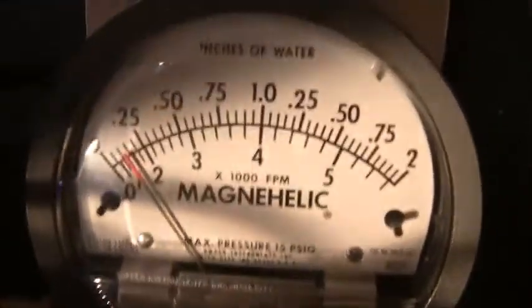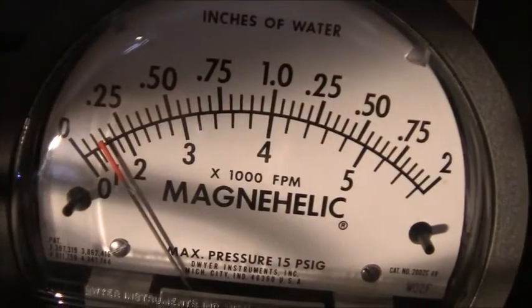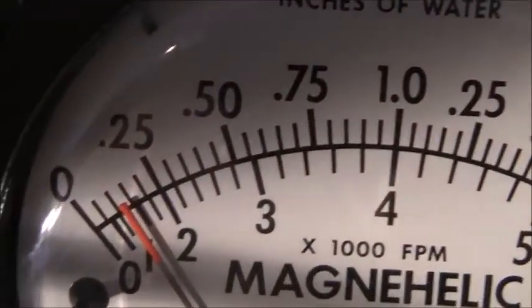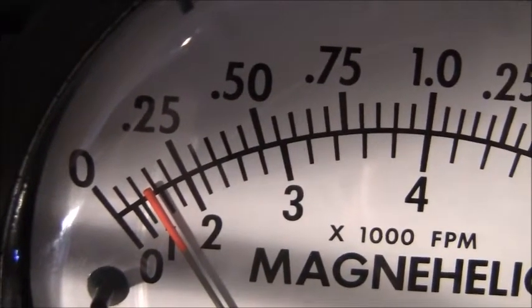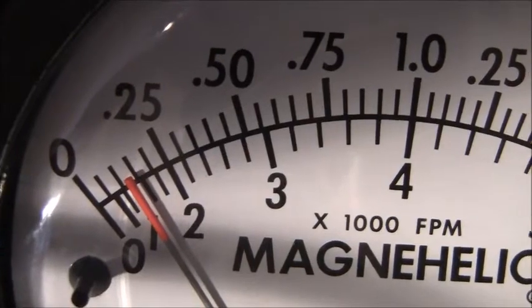On the side of the furnace, over here, I drilled a hole earlier so I could put my reading into. Okay, so now I'm going to take this, find that hole if I can. Okay, there it is right there. I found it. I'm going to go in. Now there's the reading on the Magnehelic gauge after the filter, before the fan. That number is 0.125.